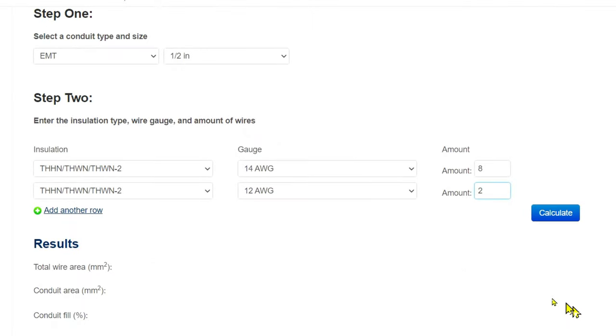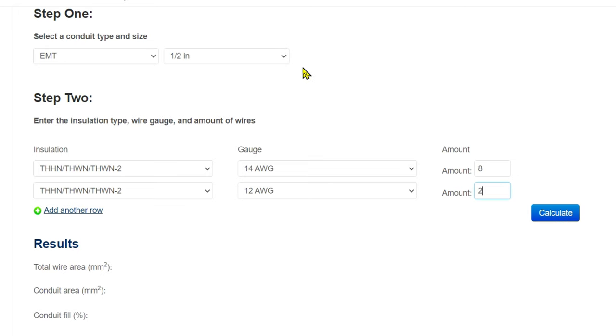This is a conduit fill calculator, and I have it set up here to EMT, half-inch, and here we are: THHN, 14 gauge—we've got eight of those; THHN, 12 gauge—we have two of those.